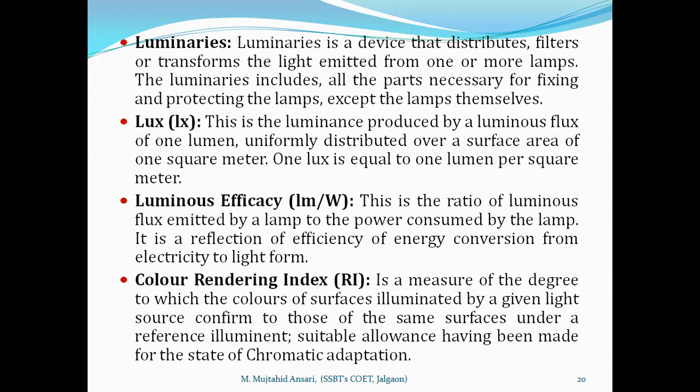Similarly, if you are using the luminaries in petrochemical industries and some pharmaceutical and chemical industries where ethane, methane, explosive gases are there, we cannot use the regular light fitting or those used for outdoor purposes. It should be flame proof. Flame proof means that whatever short circuit or fault occurs inside the lamp, whatever flames or sparking there are inside the lamp, will not come out of the luminaire, otherwise it will catch fire.